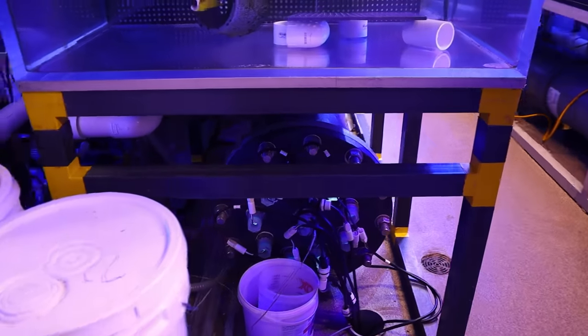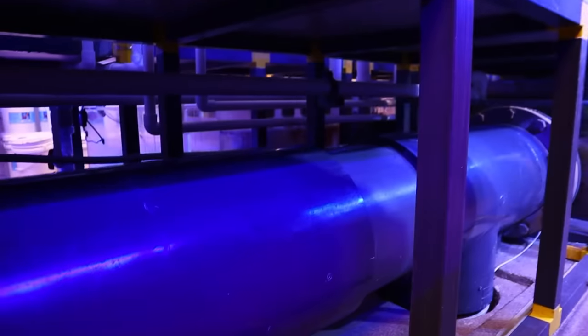Where are the UV lights? Here — you want to get a tan? Go lay in that pipe. It's 10 units, 400 watts each. We change them more often than once a year — we're on an eight to nine month program.